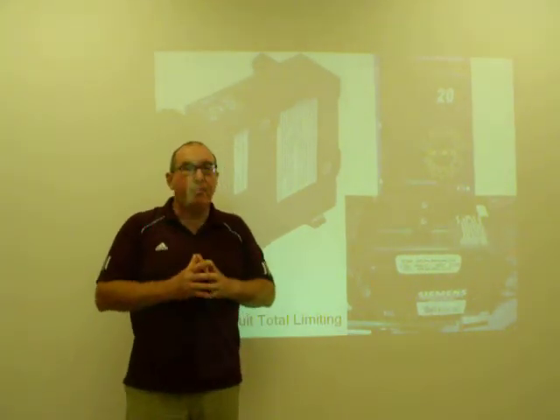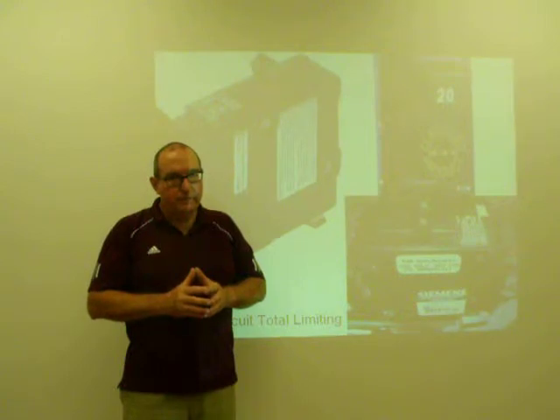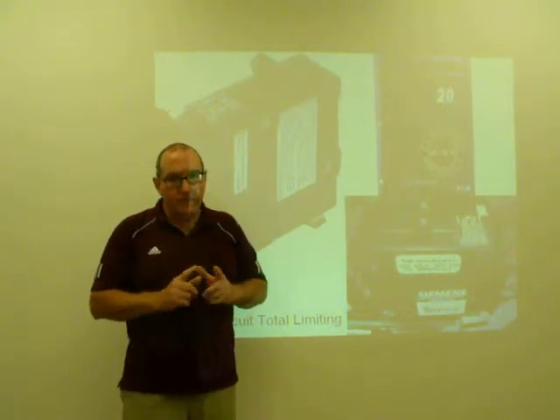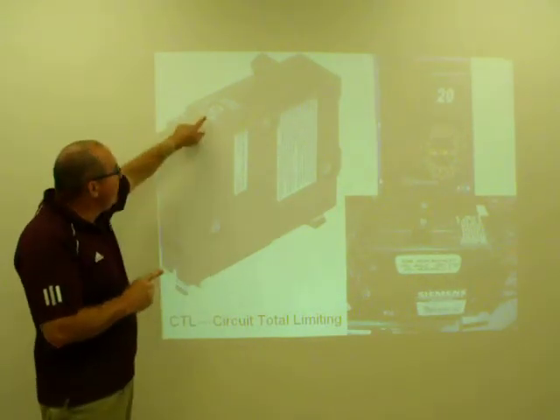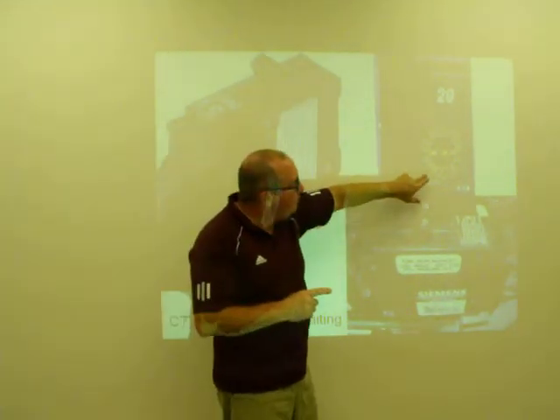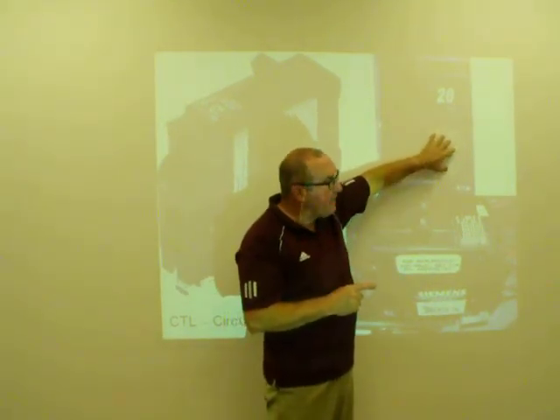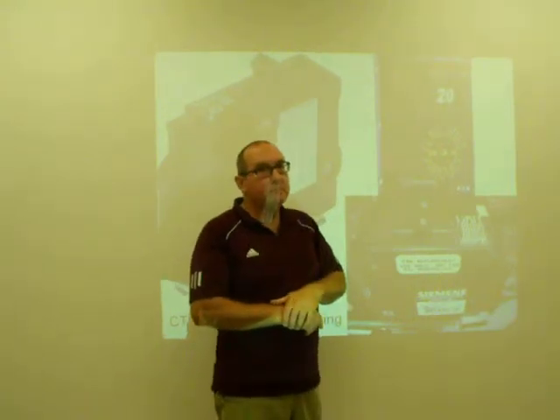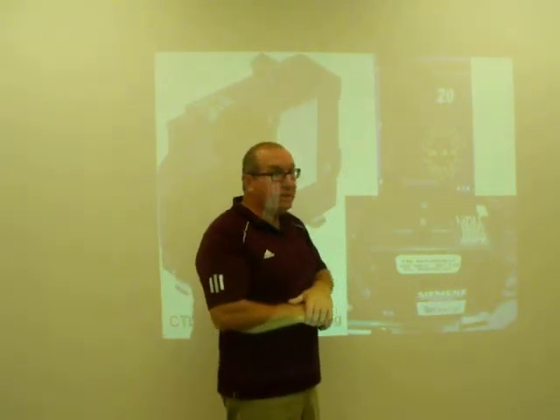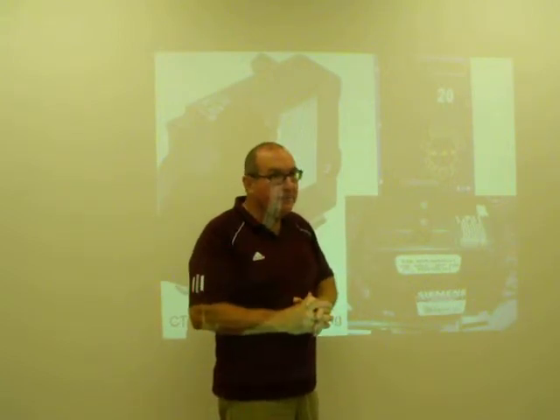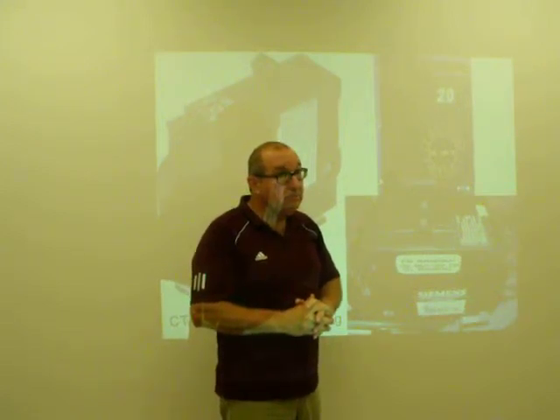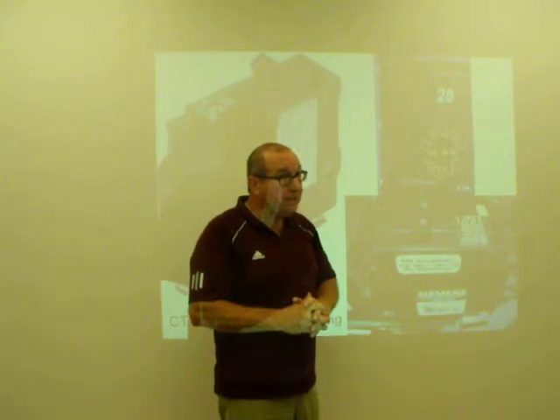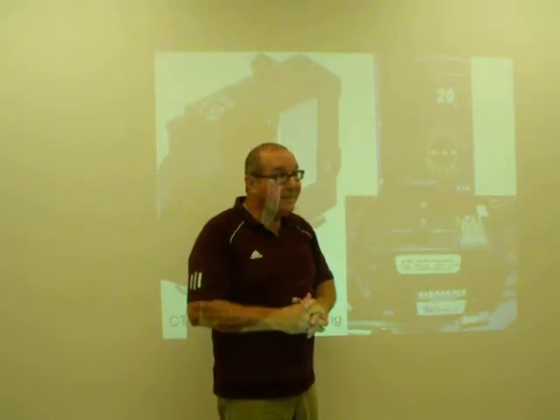Classified breakers are readily apparent in terms of their difference from a non-classified breaker in one major sense. You will find a stamp that is put on that breaker at the factory that says it's a classified product. Now, you may have two breakers that are identical in terms of putting them side by side, looking at them, made by the same manufacturer. One's classified and one isn't. So that would imply that the one that is classified is for replacement use, and the one that is not classified is for original equipment use, or replacement in that manufacturer's brand panel board and no one else's.